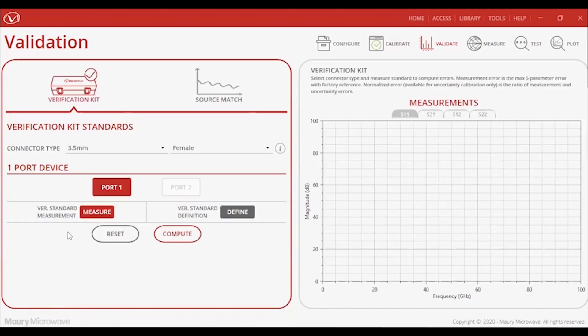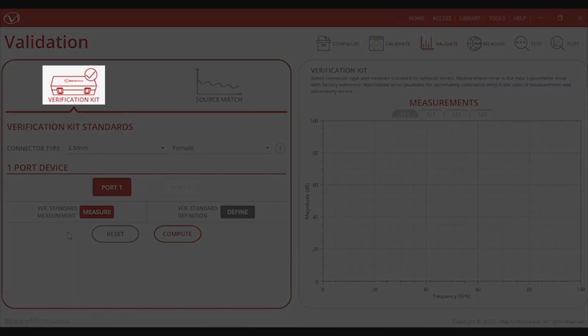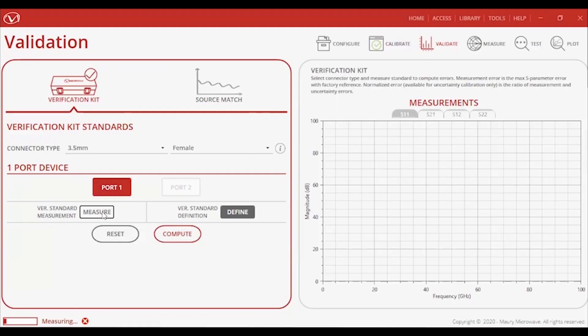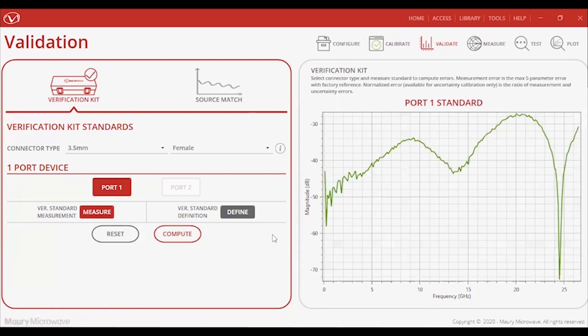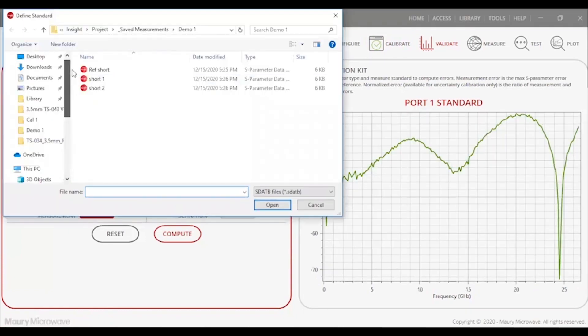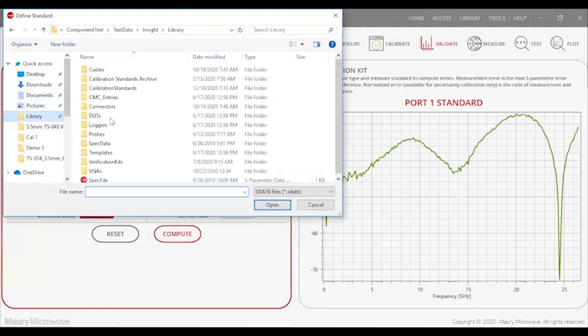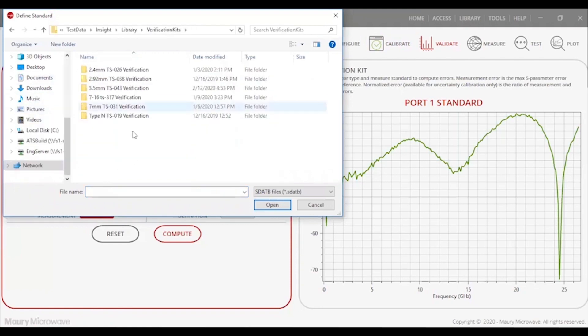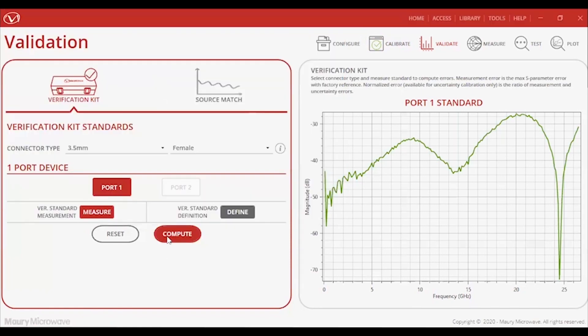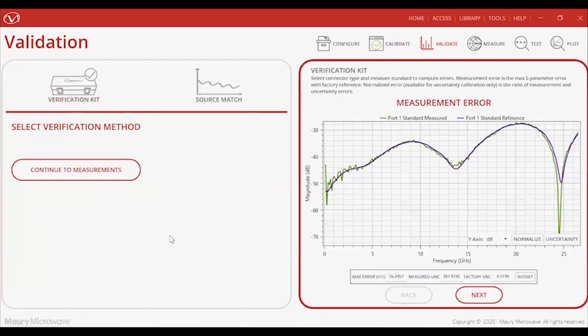In the Validation tab, you have the option to choose between Maury's verification kit or the commonly used method of source match. For this video, I'll just be covering the verification kit briefly. Under this section, I can verify my calibration either using a one or two-port verification standard, choosing between the load or short for the one-port verification, to the match or mismatch beaded airlines for the two-port verification.